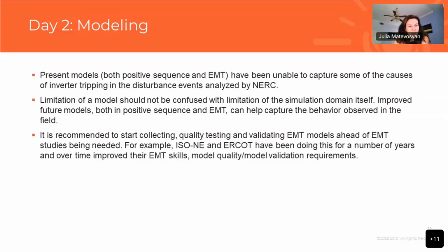It is recommended to start collecting, quality testing and validating EMT models ahead of EMT studies being needed. For example, ISO New England and ERCOT have already been doing this for a number of years, and over time they improved the EMT skills and also model quality and model validation requirements. So it takes time to collect models, to validate models, to obtain skills in using EMT tools, and so it's too late to start collecting models when the study is needed.